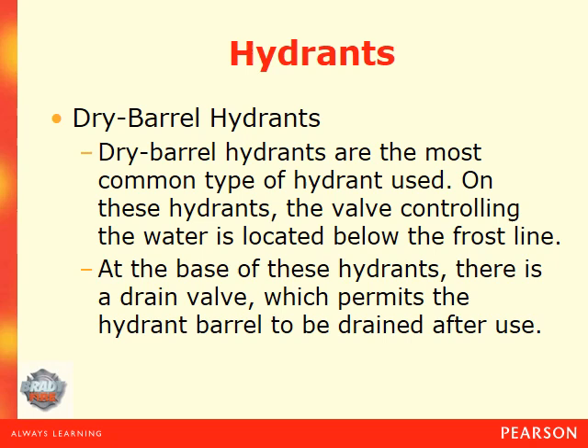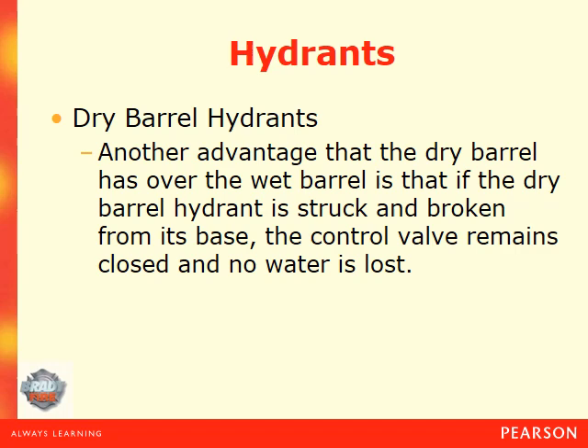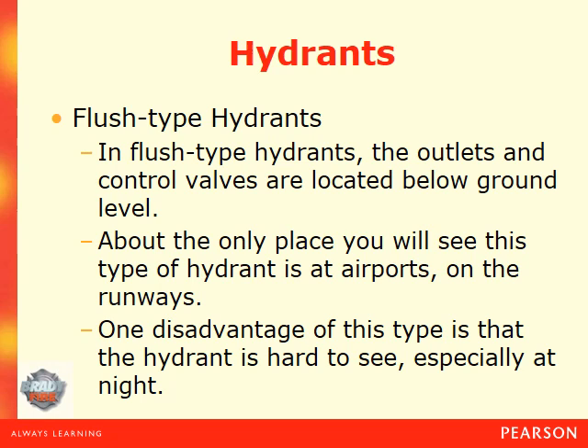In a dry barrel hydrant, the valve controlling the water is located below the frost line. At the base of these hydrants there is a drain valve which permits the hydrant barrel to be drained after use. Essentially, there is a valve below the ground; when you turn the hydrant at the top it causes that valve to open, allowing water to come up out of the feeder lines into the hydrant. After use, you close the hydrant and the water is allowed to leak out through the drain valve. Another advantage of the dry barrel hydrant is that its control valve remains closed and no water is lost if the hydrant is broken and knocked off its base.